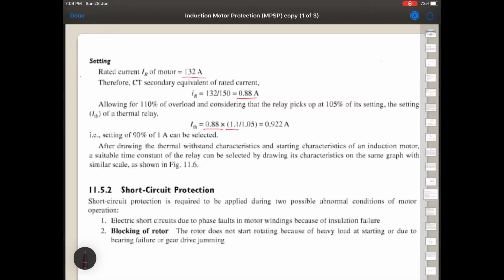110% means if you have 1 ampere, you can allow the motor or the relay to operate till 1.1 ampere. But right now, according to the ratio, since it is not operated at 150 ampere, it is operated at 132 ampere, it has been reduced to 0.88. And as I said, the relay picks up at 105%, so it is a dividing factor, so it is divided by 1.05, and we get this answer. So a point somewhere near 0.9, therefore a 90% of 1 ampere setting has been selected.